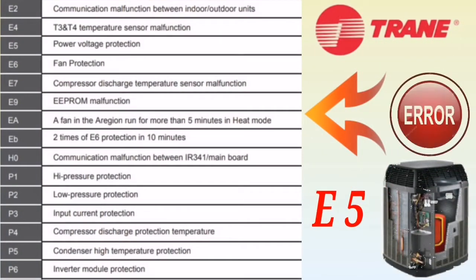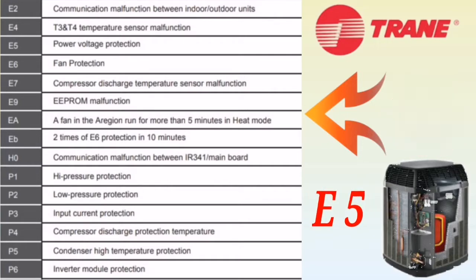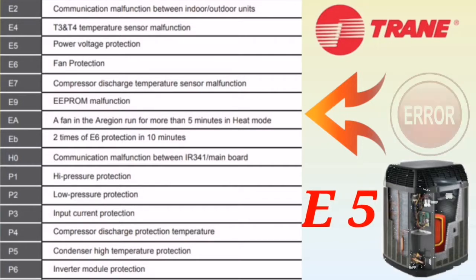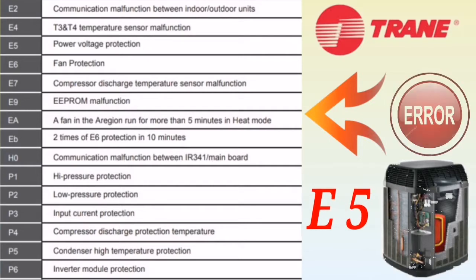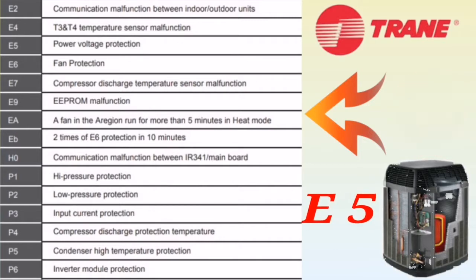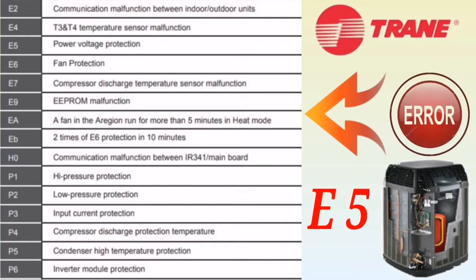The next error code is E5, which means power voltage protection. This occurs due to fluctuation of the power supply. If the power supply to the indoor and outdoor unit is not coming properly at 220 to 230 volts, it will show this error. You have to check and stabilize the power supply to resolve error E5.